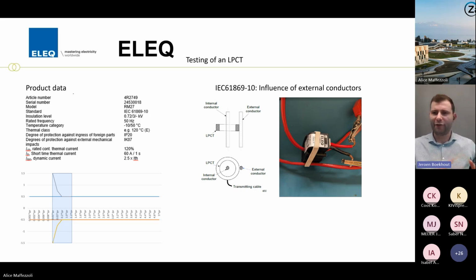So that means if we have a 5 amp primary and we make a 5 amp external conductor, the influence on the ratio error is allowed to be 1/3 of the 0.5% that is allowed at nominal current. So that means 0.1666, etc. percent of ratio deviation is allowed. This is extremely important because, as you saw already in the pictures from Isabel, they are positioned in a very crowded compartment with multiple cables and multiple signals. So having this test within the -10 is extremely important to ensure reliability in these types of applications.